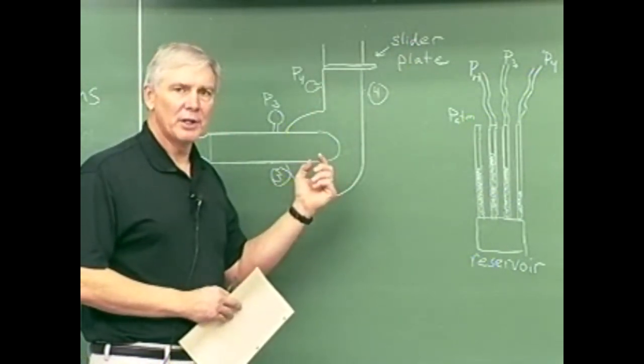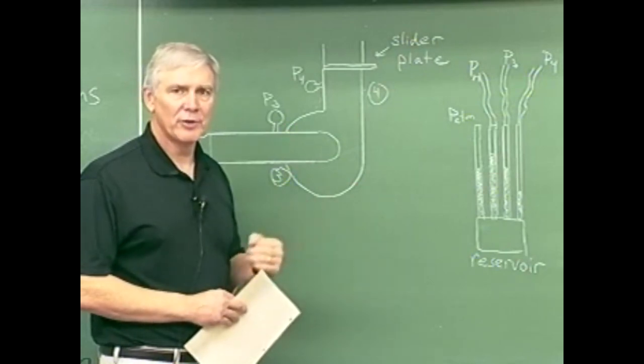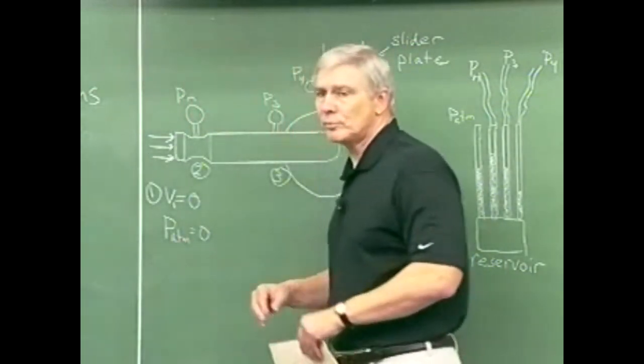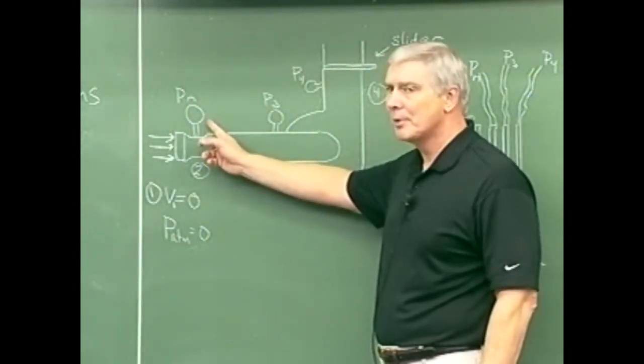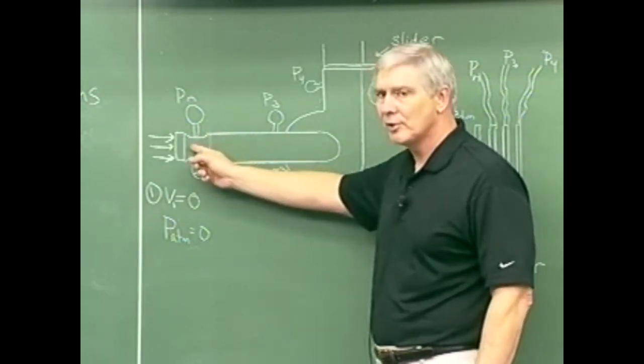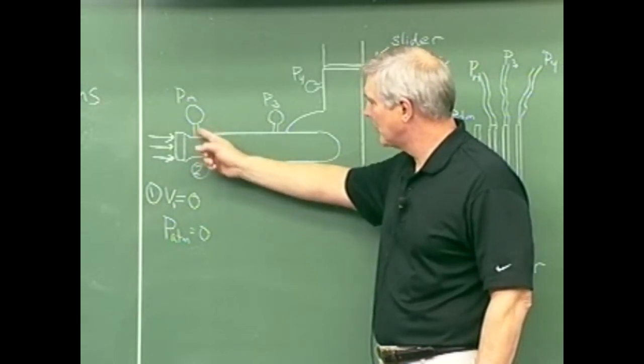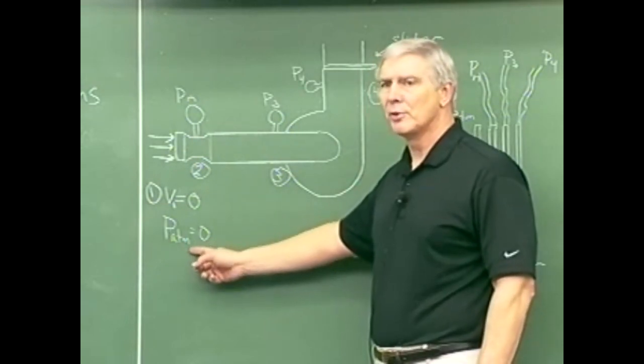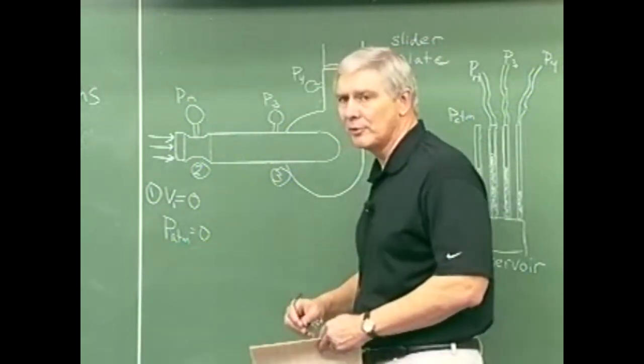We're also going to need the velocity or we actually need the flow rate coming into the fan. And the way we get the flow rate coming into the fan is over here we have a nozzle. And the nozzle is also instrumented with a pressure tap. And the nozzle has a contraction section here so as the flow comes through the pressure decreases. And we can measure the difference between the flow or the pressure at the nozzle and the pressure at the room. And using Bernoulli's equation, we can get the flow rate.